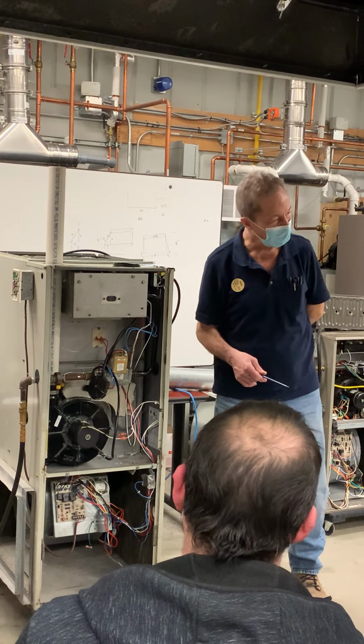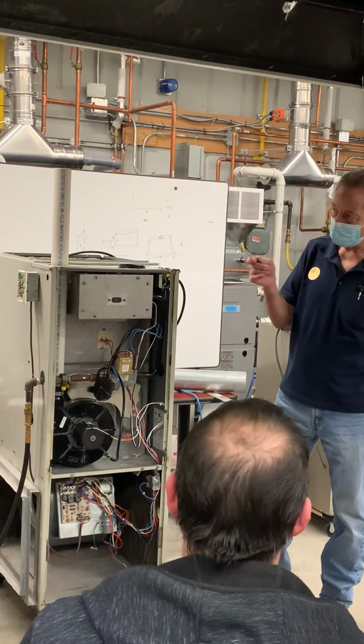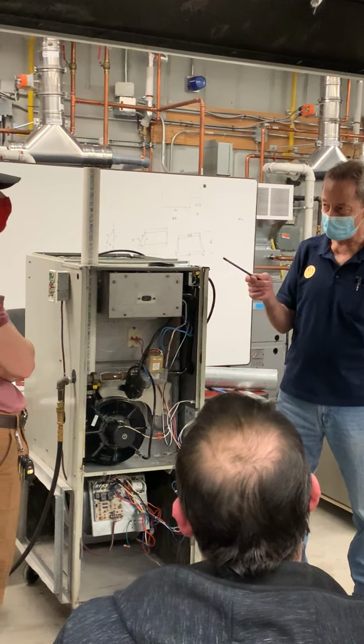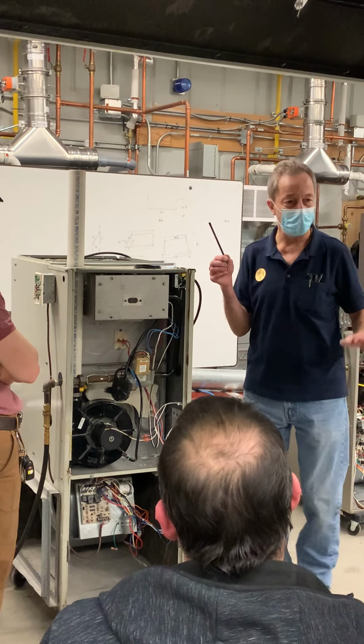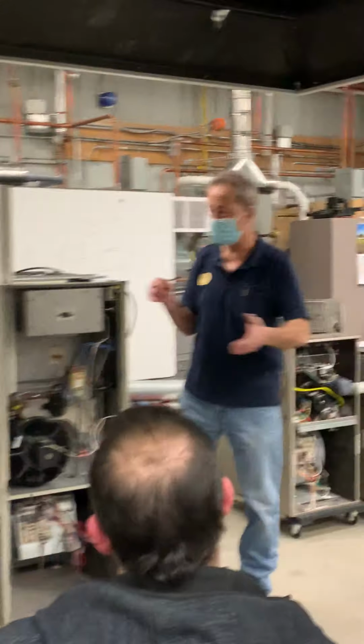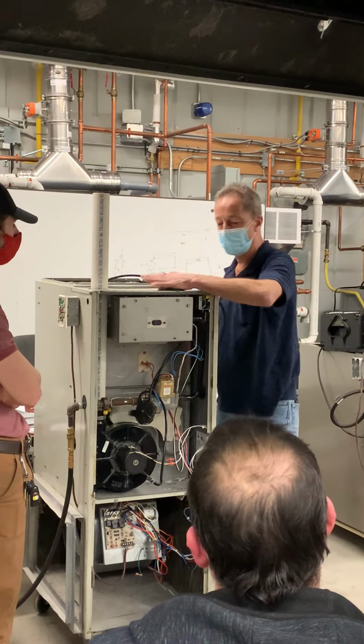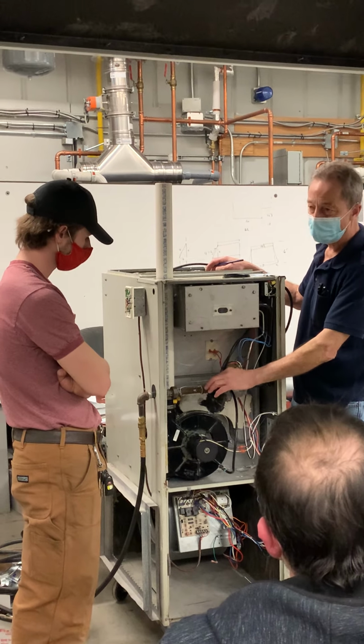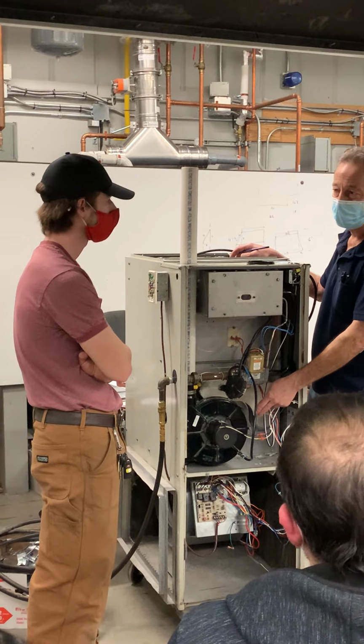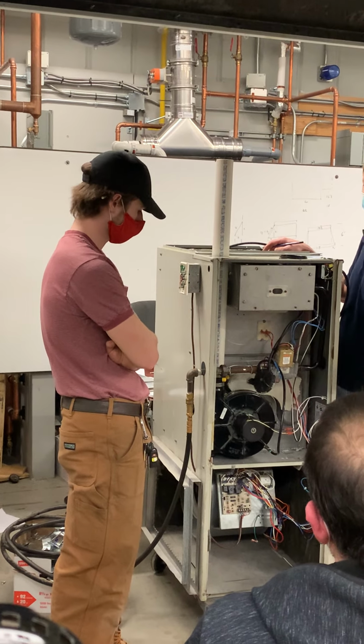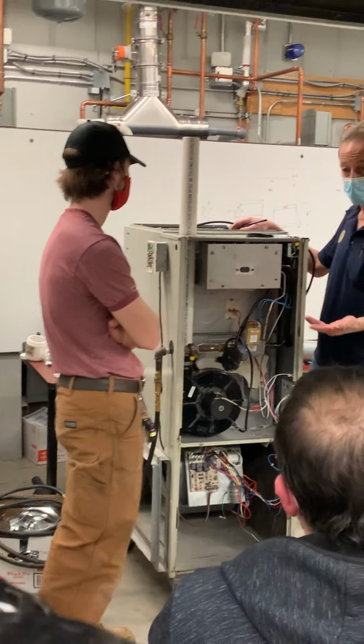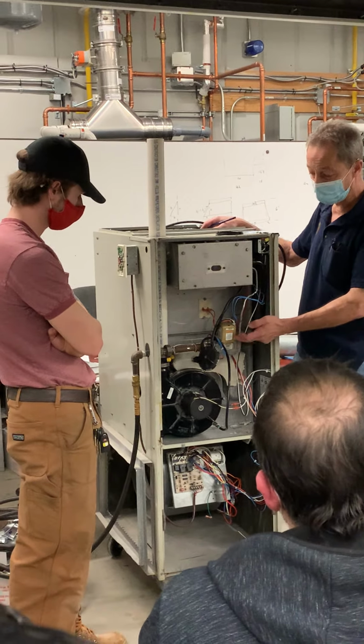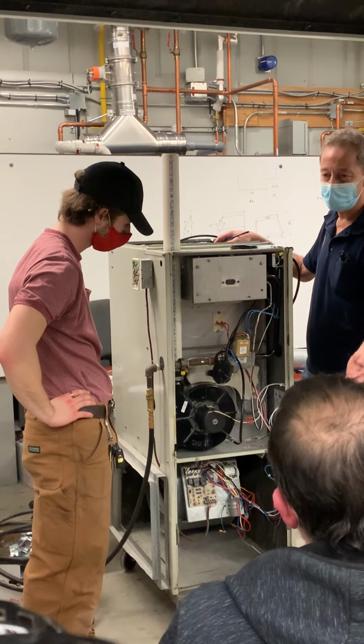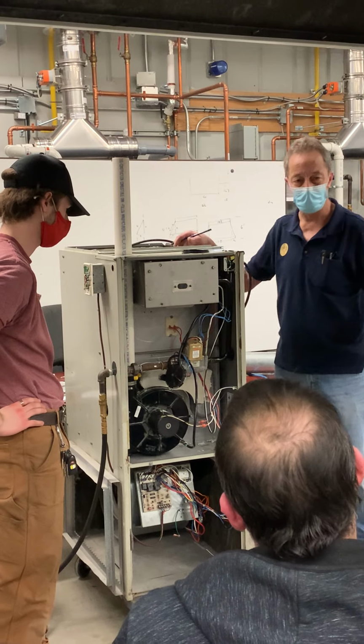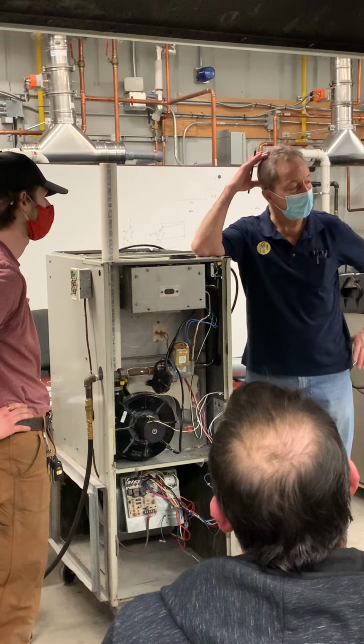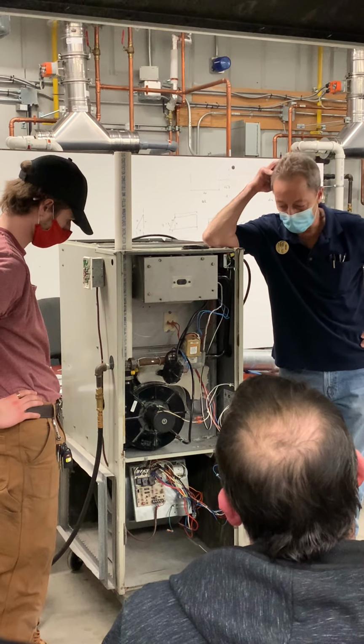Okay, now here's another question for you. I said earlier to you, a blocked secondary heat exchanger. So we were talking about defects that would cause it not to proceed on the sequence of operation. So we said a blocked vent, blocked intake. We said defective pressure switch, problem with the hose connection, inducer's not running, inducer's not creating sufficient negative pressure. Any of those items could cause it, couldn't it? Okay, so it's not going to progress on the sequence of operation. We also know that, hey, the valve could have got 24 volt, but it just said, I'm screwed up, I'm not going to work. I did my self-check, something's not right. So you know that there's several steps there. Now let's give a little bit of thought to the process here.